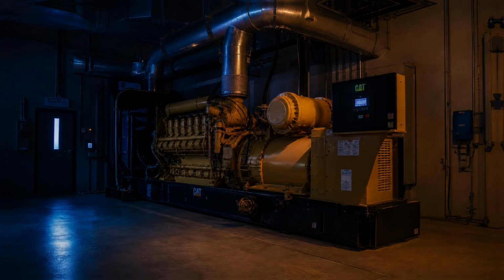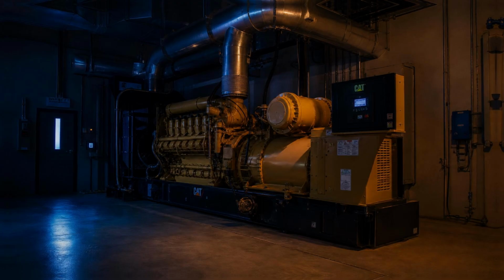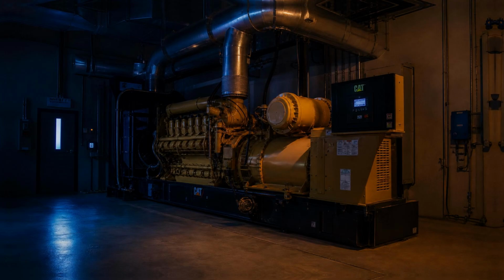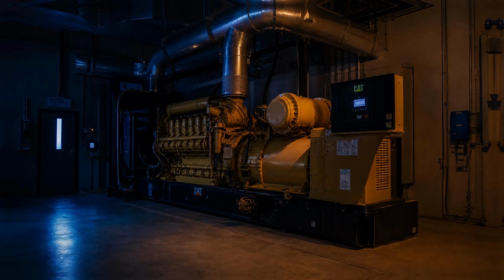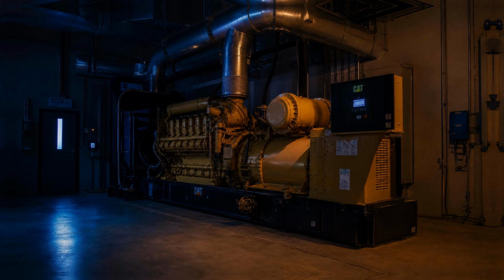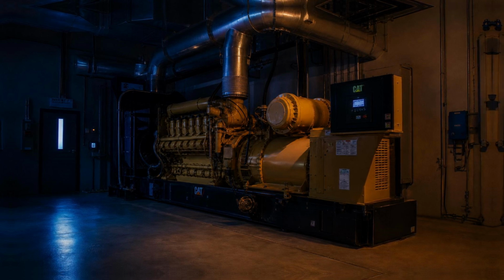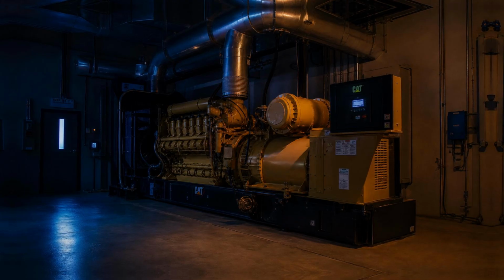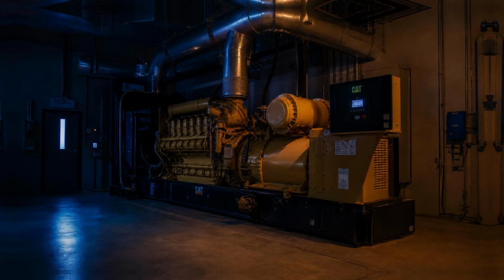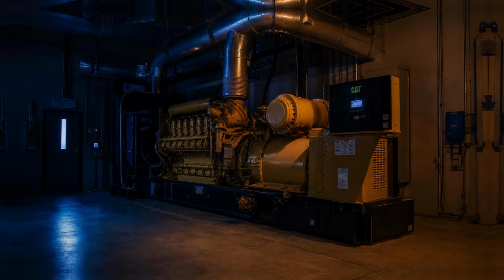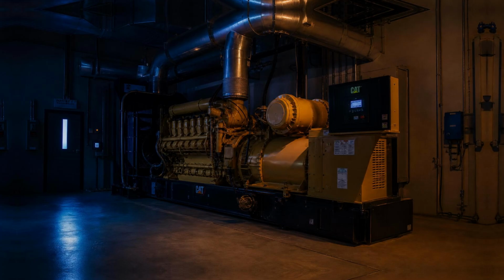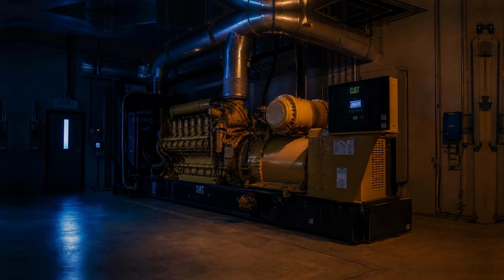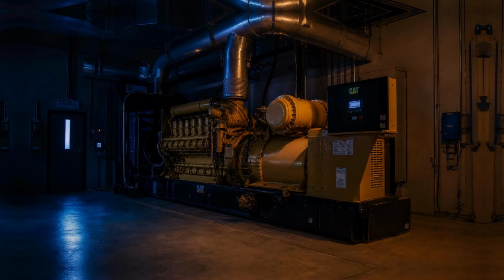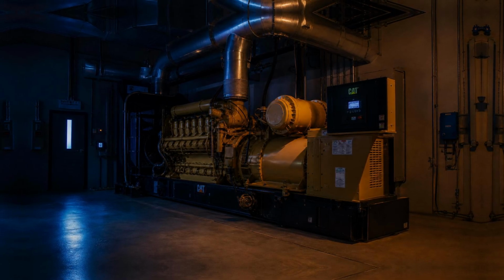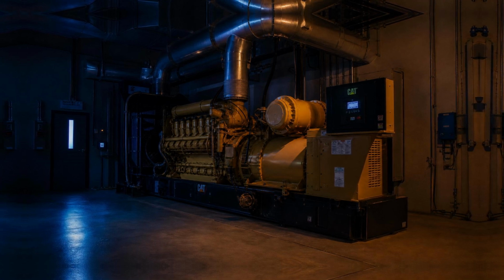A server processing a transaction, a medical monitor displaying a patient's heart rhythm, a control system managing a critical industrial process. For these loads, the gap that the generator's startup time creates is not a small problem. It is the central problem, and it is the problem that the uninterruptible power supply exists to solve. The uninterruptible power supply, the UPS, is in its most fundamental character a bridge, a span of stored energy thrown across the gap between utility failure and generator readiness, narrow enough to cross quickly but strong enough to hold whatever passes over it. It does not replace the generator.